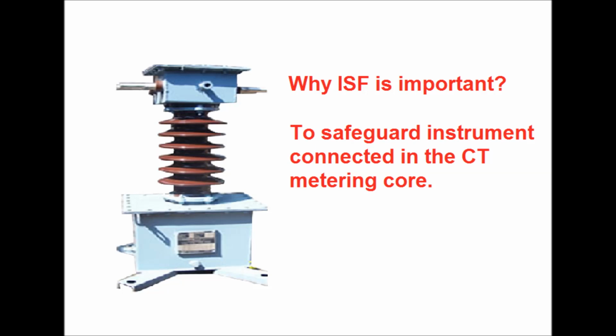So under normal conditions, the meter shall accurately give the reading of the current flowing in the CT secondary side, which is the actual replica of the CT primary current. So the purpose of this instrument security factor is to safeguard the instrument which is connected in the CT secondary side of the CT metering core.